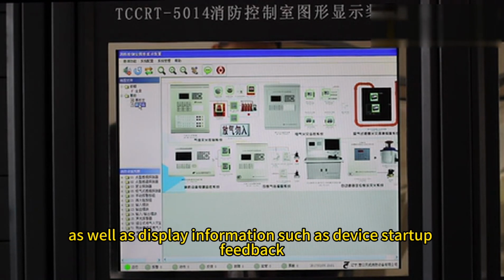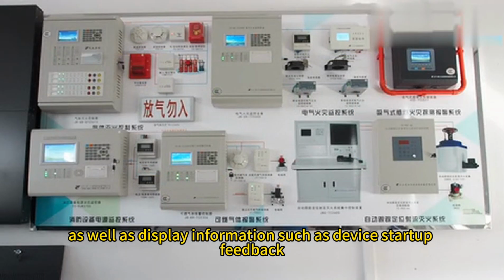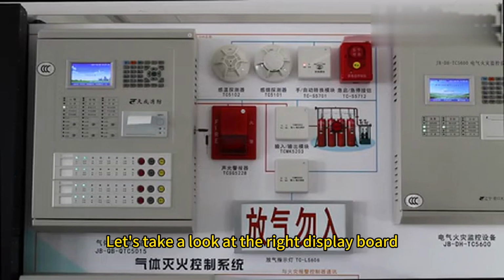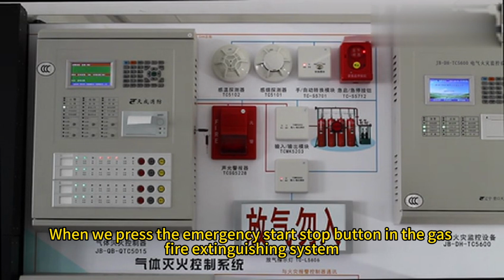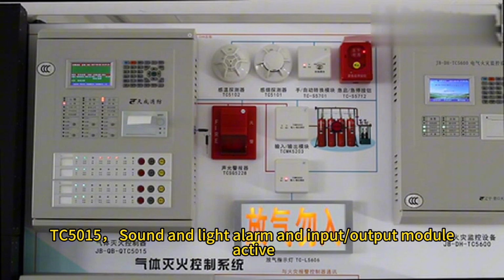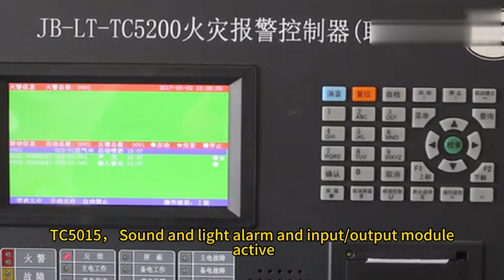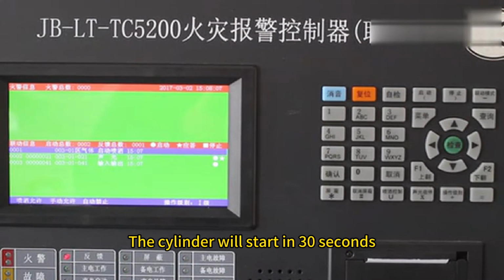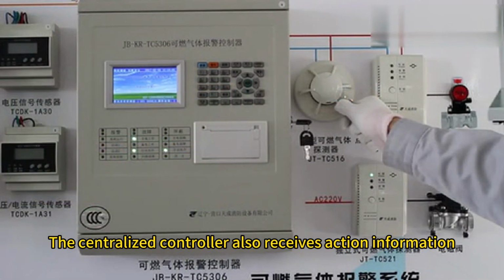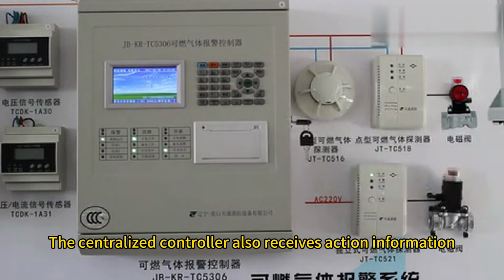Let's take a look at the right display board. When we press the emergency start-stop button in the gas fire extinguishing system, the TC5120 sound and light alarm and input-output module are activated, and the cylinder will start in 30 seconds. The centralized controller also receives action information after the detector in the combustible gas alarm system is activated.